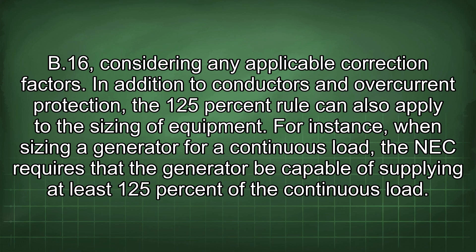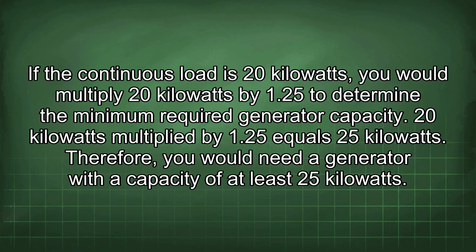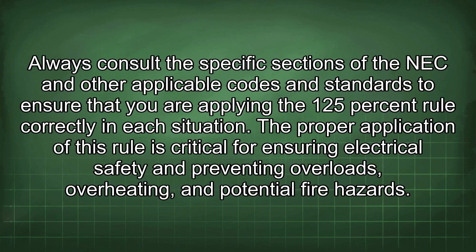In addition to conductors and overcurrent protection, the 125% rule can also apply to the sizing of equipment. For instance, when sizing a generator for a continuous load, the NEC requires that the generator be capable of supplying at least 125% of the continuous load. If the continuous load is 20 kW, multiply 20 kW by 1.25: 20 × 1.25 = 25 kW. Therefore, you would need a generator with a capacity of at least 25 kW. Always consult the specific sections of the NEC to ensure correct application, as proper use of this rule is critical for preventing overloads, overheating, and potential fire hazards.